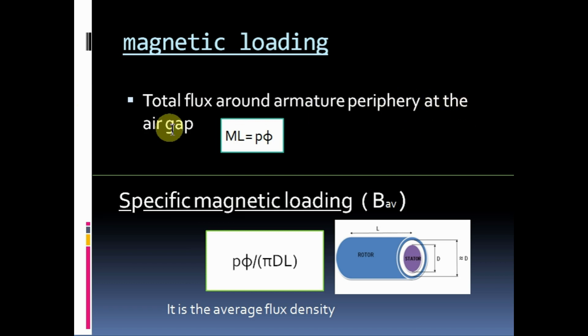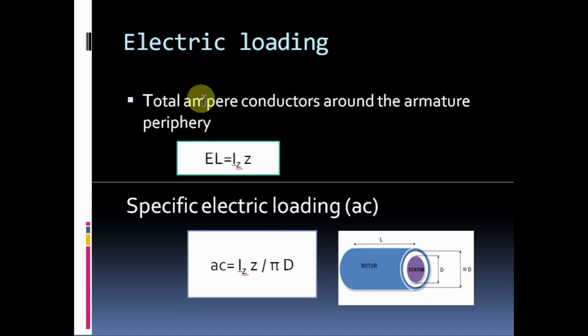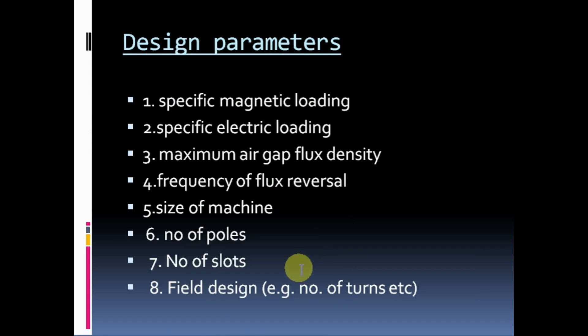Magnetic loading is the total flux around armature periphery at the air gap. ML equals P into Phi. Specific magnetic loading, B_av, is the average flux density: B_av equals P·Phi divided by pi·D·L. Electric loading is the total ampere conductors around the armature periphery: EL equals Iz into Z. Specific electric loading AC equals Iz·Z divided by pi·D.